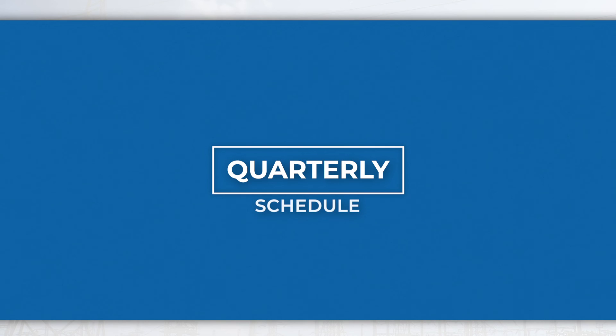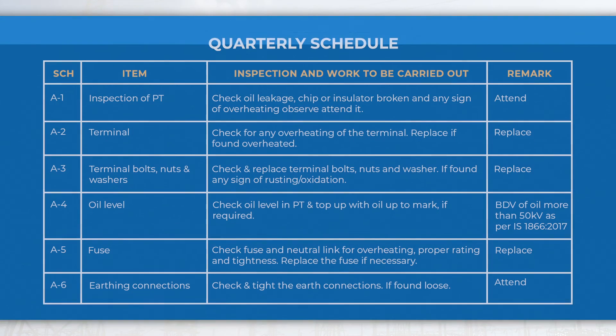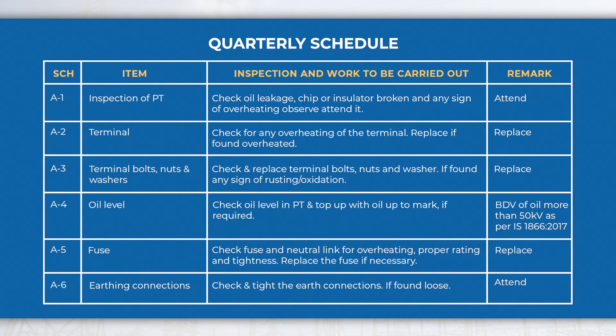Quarterly schedule: In the quarterly schedule, perform activities like checking the surface of the porcelain insulator, the terminal connector for overheating or rusting, checking the oil level in the bushing, fuse and neutral link for overheating and earthing connections, etc.